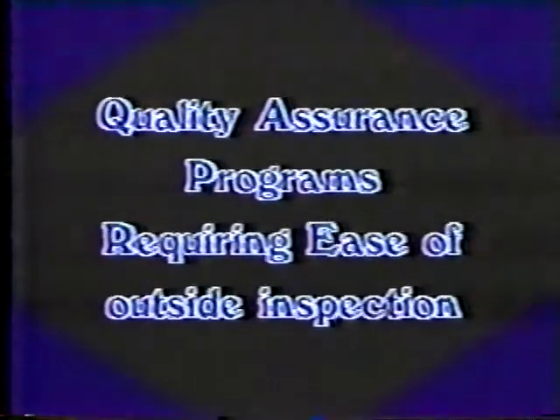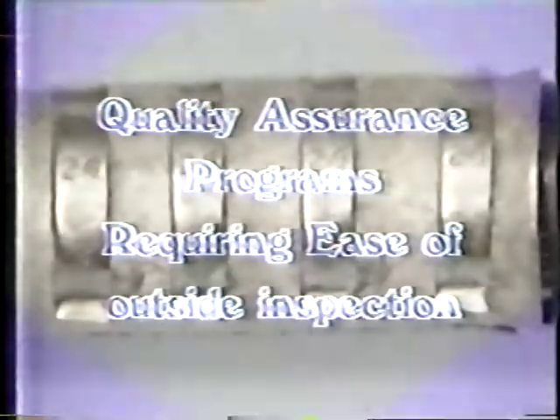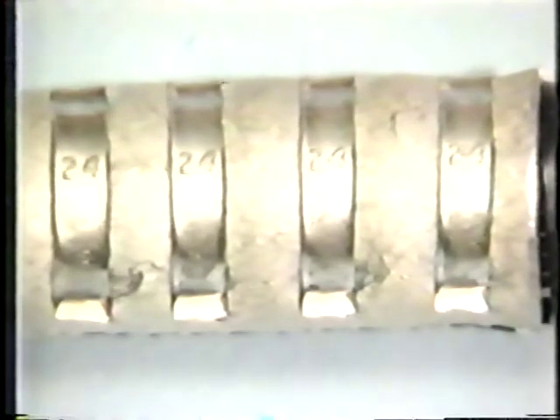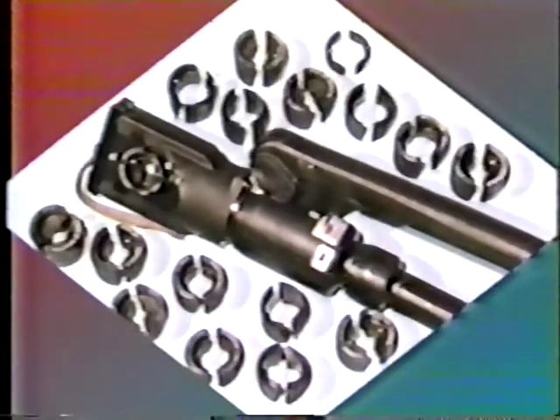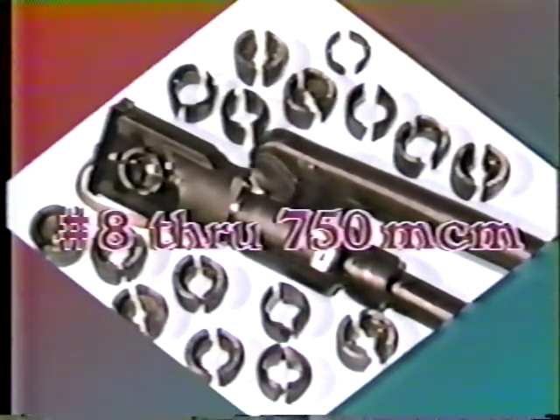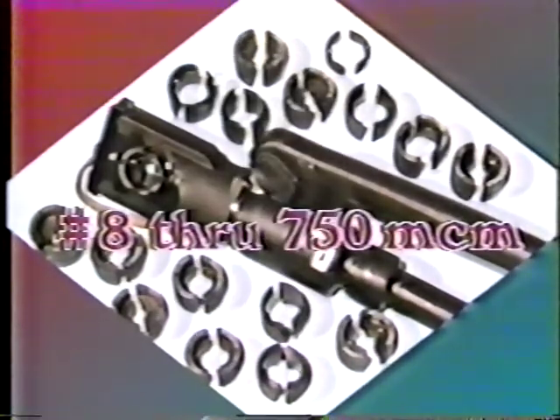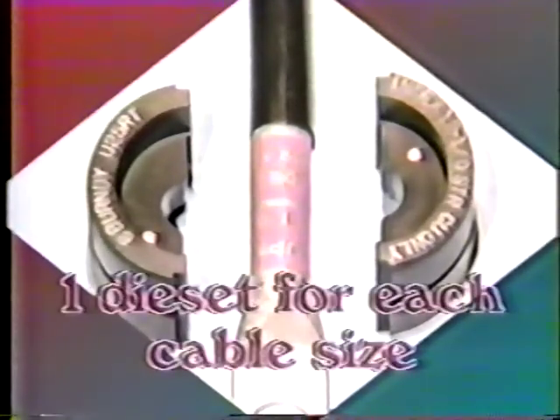In quality assurance programs where ease of outside inspection is a necessity, Burndy offers a complete color-coded die installation system, including the easy-to-use Y39 press. This system will accommodate the full range of copper and aluminum conductors from number 8 through 750 MCM. To provide instant inspectability, each die embosses a die index identification directly into the connector body. The Burndy system eliminates confusion by providing one complete color-coded die set for each cable size.